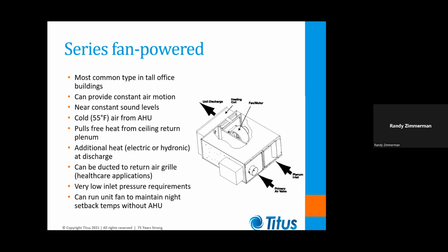And so we're going to get cold air from the air handler, and that's going to modulate the primary air based on a room sensor down on the wall of the room. And as the primary inlet closes, the fan is going to draw an increasing amount of airflow through that plenum inlet to make up for a lack of primary airflow. So you can think of fan-powered boxes like this as drawing in warm return air and mixing it with the primary air, because all of the air going out to the room is going to go through the blower.